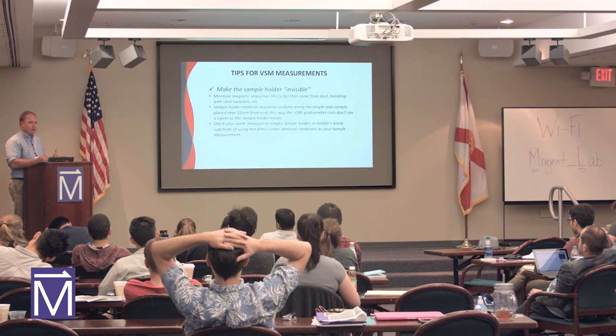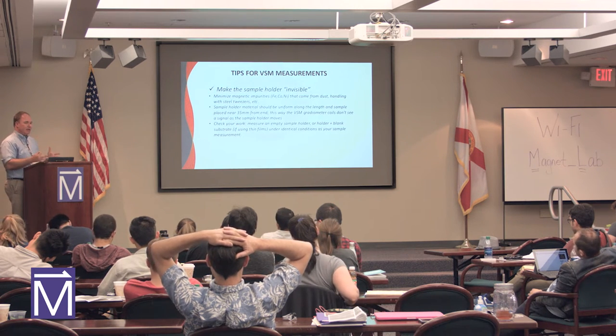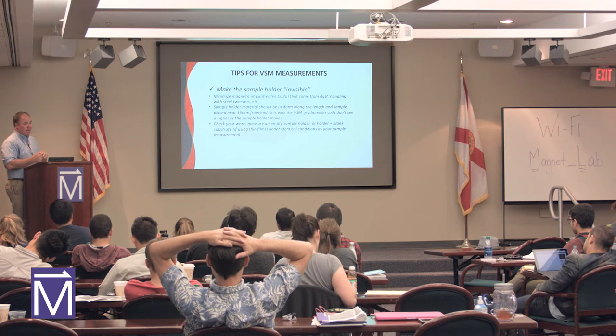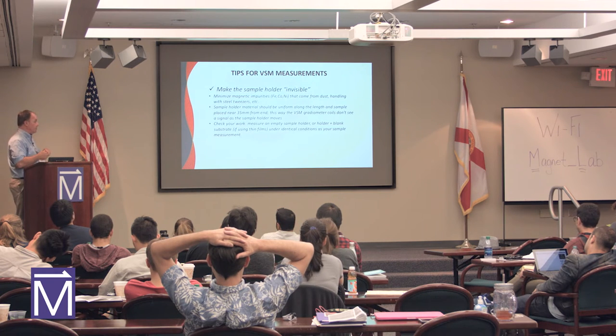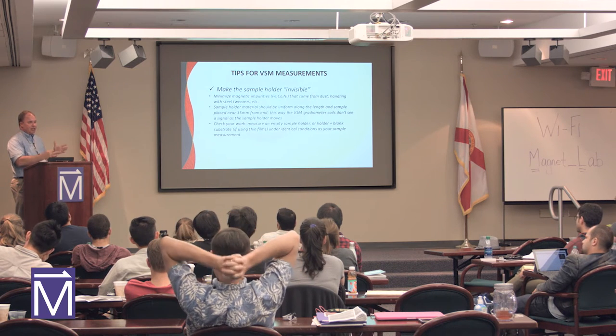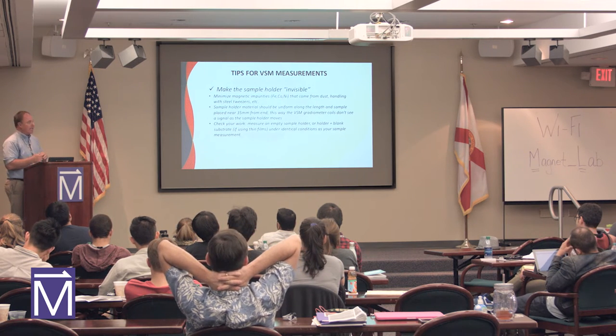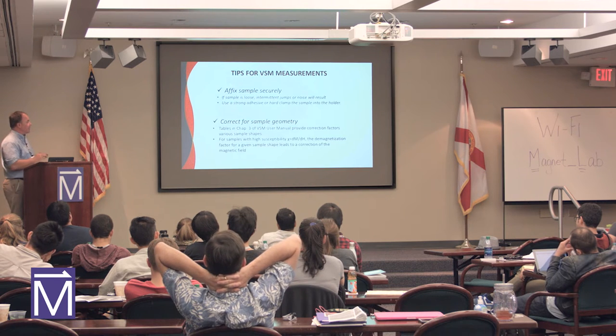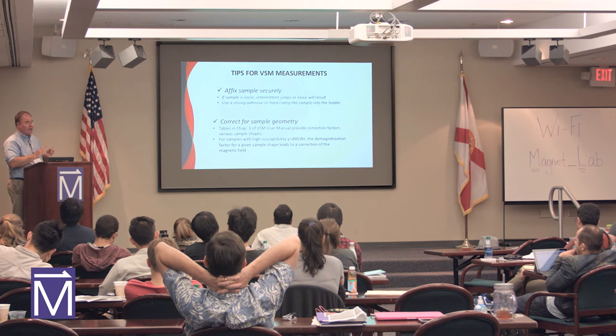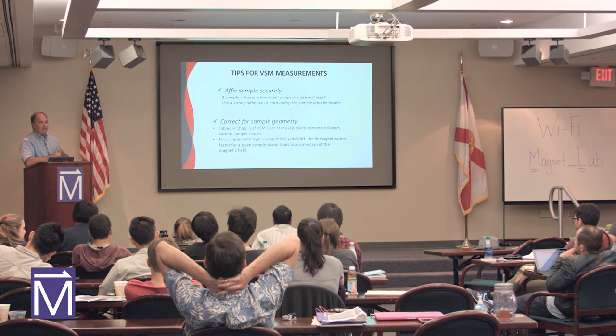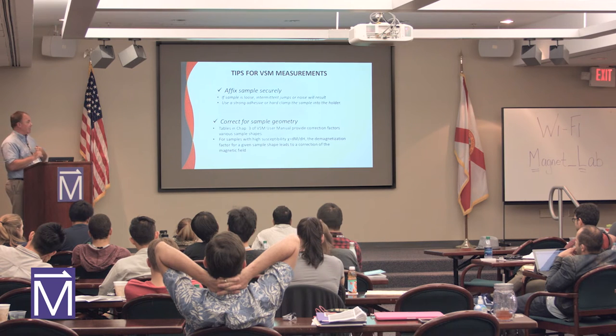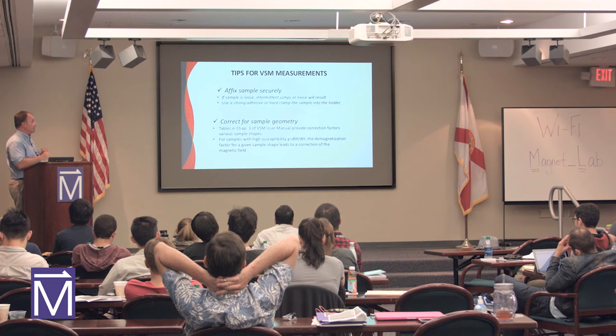For thin films, run the substrate of your thin film, because that will tell you if the substrate has a high magnetic moment, or a diamagnetism that may influence your measurement. So try to run your blank holder as a sanity check against your holder plus sample. That's always a good thing. So make it invisible. Make sure the sample's mounted correctly. Is it mechanically mounted correctly? Did you use the right adhesive? Does the adhesive have a magnetic signature? So make sure you run your adhesive if you're using that, or your Kapton tapes.